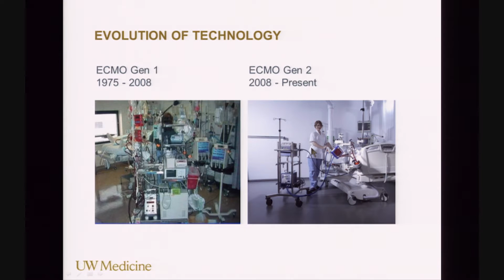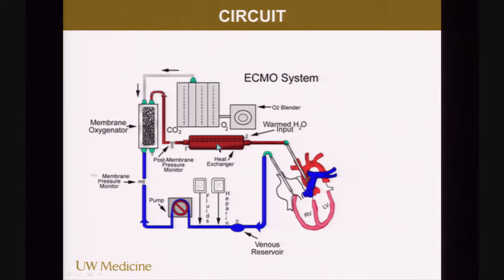So what are the components of the system? Basically, blood comes out of the venous system or the arterial system. In this, it always comes out of the venous system. It goes through the pump, goes through a membrane oxygenator, and that's where gas exchange occurs. It goes through a heat exchanger, and the heat exchanger is really valuable because it allows you to tightly control the temperature of the patient. So for patients that are hypothermic that you want to rewarm, you can rewarm them very effectively. For people you want to keep cold for whatever reason, you can do that as well.